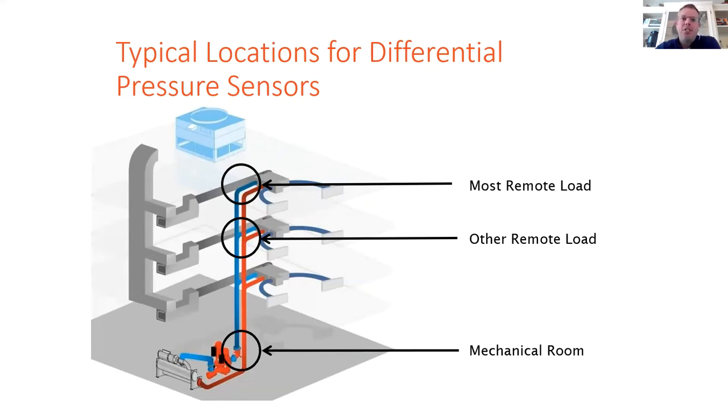The last location is often used in retrofit applications and when an engineer doesn't specify an exact location of the sensor, which is in the mechanical room or between the pump and the first load. So the minimum head pressure set point is then basically set at the pressure drop of the entire piping system and allows very little turndown.